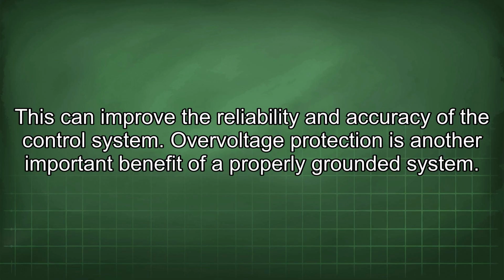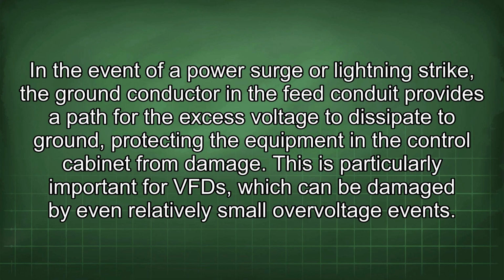Overvoltage protection is another important benefit of a properly grounded system. In the event of a power surge or lightning strike, the ground conductor in the feed conduit provides a path for the excess voltage to dissipate to ground, protecting the equipment in the control cabinet from damage. This is particularly important for VFDs, which can be damaged by even relatively small overvoltage events.